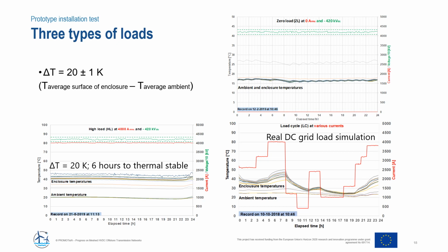So here you see the enclosure temperature being higher than the ambient temperature by a little bit more than 20 degrees Celsius. And on the right top, you see the zero load testing block. Just for certain hours, of course, the temperature is ambient as you see here, and there is no current, only the voltage has been applied, a voltage of 420 kV, in this case negative polarity. The third test, which was in 15 day blocks, is a load cycle where current has been varied between zero load and high load as you see. So a specific load profile for 24 hours has been specified, and that is followed to see the temperature of the enclosure, which you see varying according to the current in this case.